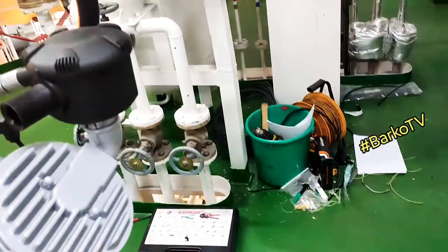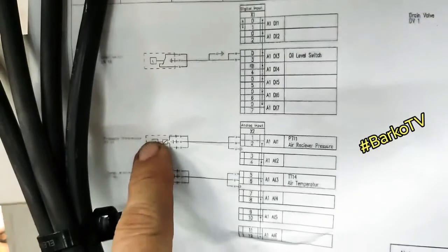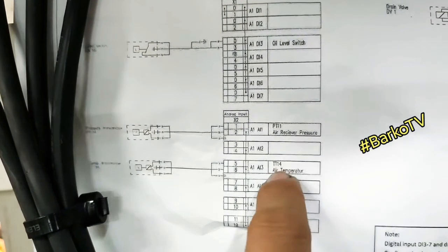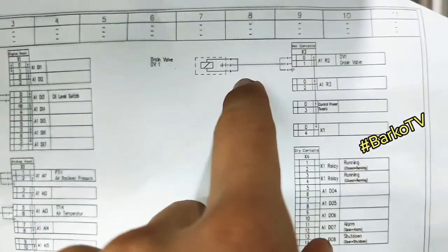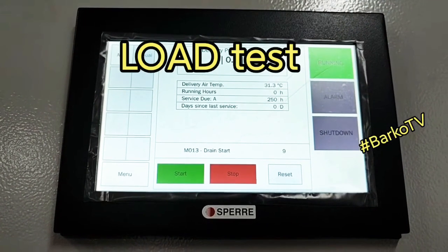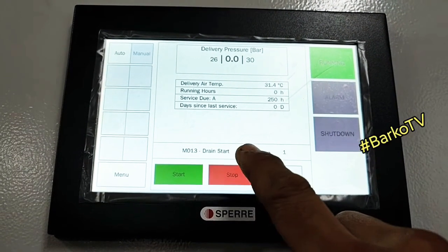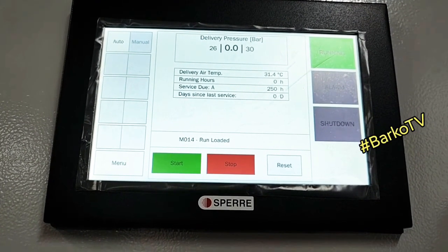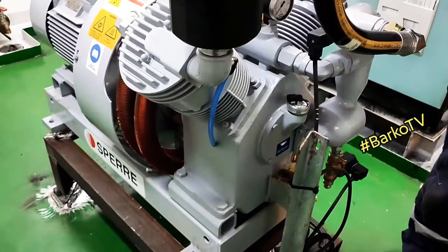The motor manufacturer is Hoyer. The emergency compressor brand is SPERRE — S-P-E-R-R-E. Leave a comment if you know the correct pronunciation. Now starting the load test: the cut-in is 26 and the cutout is 30. As you can see, the compressor is loaded and on load.